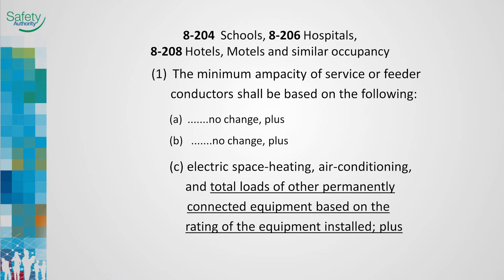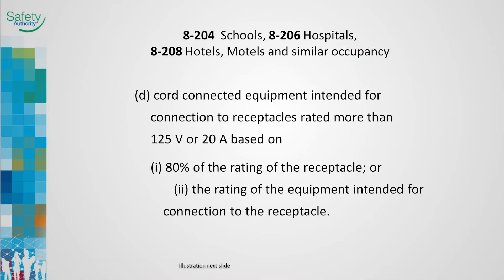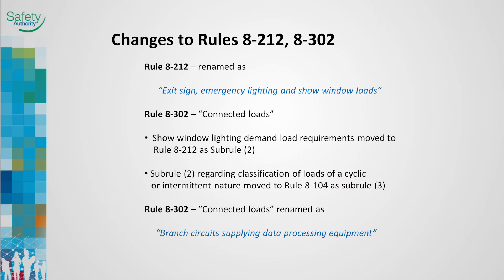Rule 8204, Schools; 8206, Hospitals; and 8208, Hotels, Motels and similar occupancies: the 2012 code wording in Item C, Power Loads, has been replaced with wording which includes more electrical equipment typically found in modern schools. Including these loads will result in a more accurate calculation when determining the minimum capacity for a service or feeder supplying loads in schools, hospitals and hotels and motels. Item D is also new and has been included to account for the large loads that cord-connected electrical equipment can add to an electrical system found in schools, hospitals, hotels and other similar occupancies. Only loads rated more than 125 volts or 20 amps must be included. These editorial changes were made to either group similar loads within the same rule or to group certain load classifications such as cyclic or intermittent within the same rule.